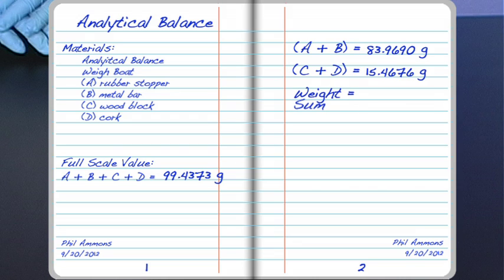Now add the two values together to get 99.4366 grams. This total is called the weight sum. If the balance is exactly linear at its midpoint, then the weight sum will equal the full-scale value.